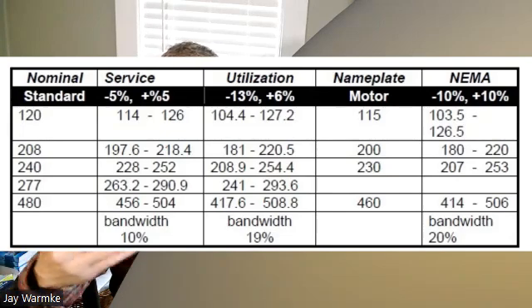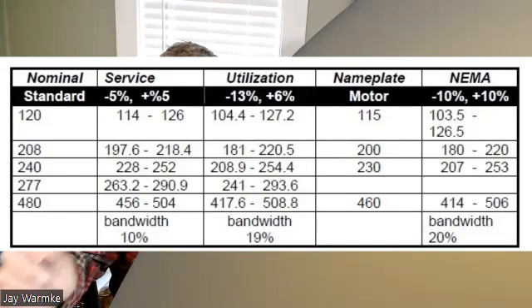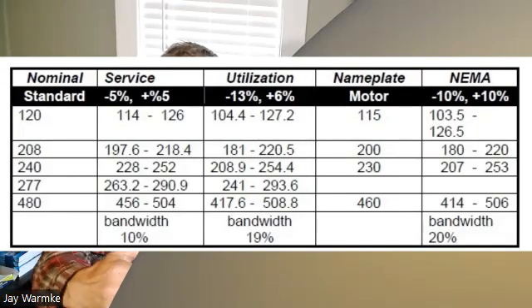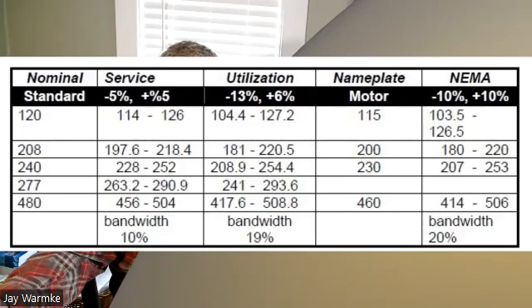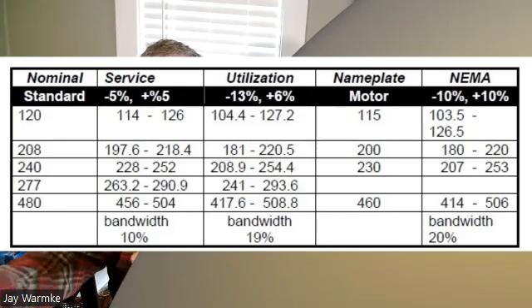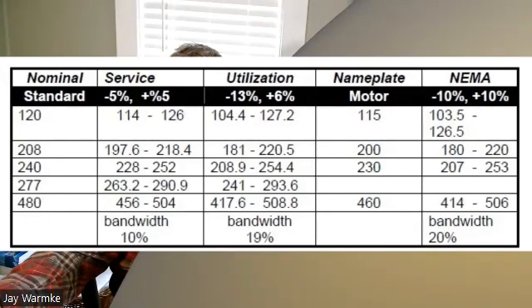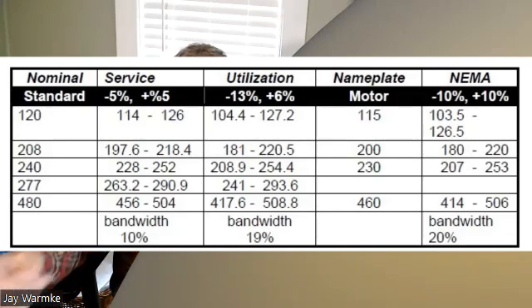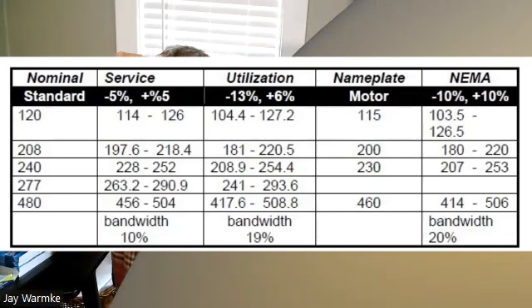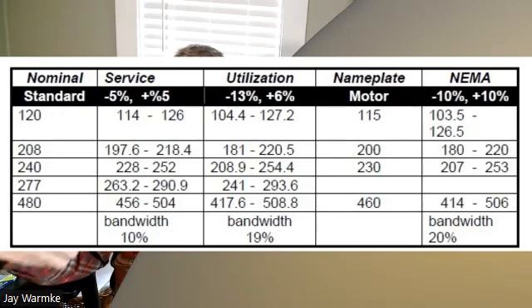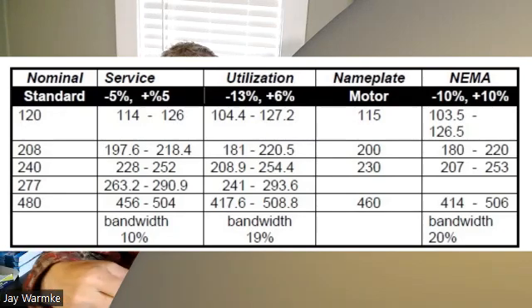They have another layer, they call it their utilization area, but basically it says for brief periods of time, the grid can operate at a -13 and a +6. So it could veer outside of that plus or minus 5 for just a brief period of time, and it's still not going to shut down. So in that case, now we're down to say about 209 and all the way up to 254 volts, and it will still operate there at some point.